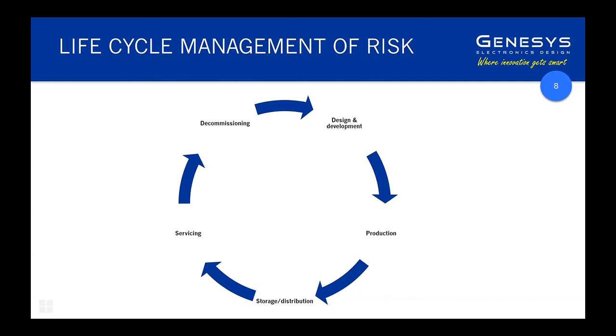So the risk management standard has clauses, and it's your job to figure out how you're going to comply with those standards. You can cut and dice it how you want, but what you tend to find is there are some common elements, because it makes it easy to find things and navigate the standard. I'm going to give you some examples of things you would typically expect to see in a risk management file. You would need a risk management procedure, for example. You would need a risk management plan. These are documents that are reviewed and approved.